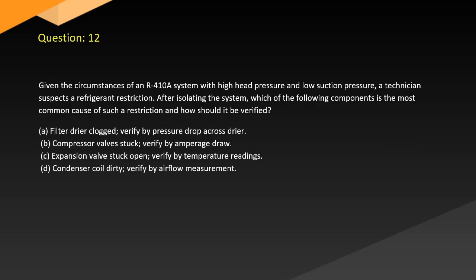Question 12. Given the circumstances of an R-410A system with high head pressure and low suction pressure, a technician suspects a refrigerant restriction. After isolating the system, which of the following components is the most common cause of such a restriction and how should it be verified?